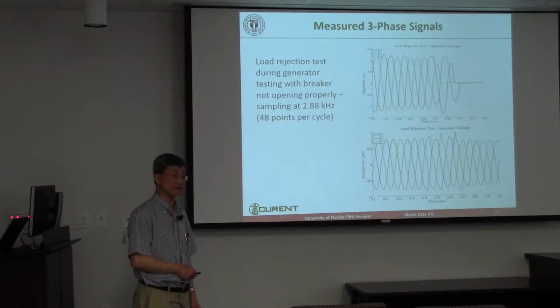Afterward, we didn't know what was going on, so we recorded this, and I analyzed it and showed it to the station engineer. He looked at it and wasn't really happy. After we did the test, he had people open up the circuit breaker and found the broken pieces, and replaced it immediately — because if the circuit breaker doesn't open properly, and you have a short circuit right next to a generator, it will damage and ruin the generator.